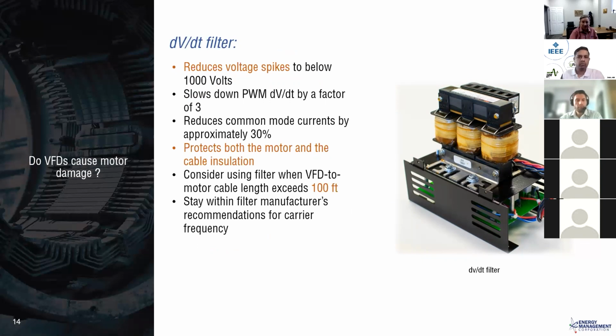Typically in the past, the thing that has been done has been applying a dV/dt filter. Actually, I'd go back maybe over 20 years ago, Allen-Bradley and others had a filter, and we actually built some, called a motor termination filter, where you're trying to match that impedance to suppress that waveform.